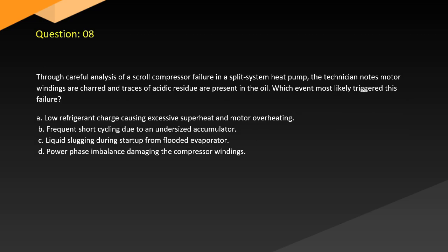Question 8. In a careful analysis of a scroll compressor failure in a split system heat pump, the technician notes motor windings are charred and traces of acidic residue are present in the oil. Which event most likely triggered this failure? A. Low refrigerant charge causing excessive superheat and motor overheating. B. Frequent short cycling due to an undersized accumulator. C. Liquid slugging during startup from a flooded evaporator. D. Power phase imbalance damaging the compressor windings.